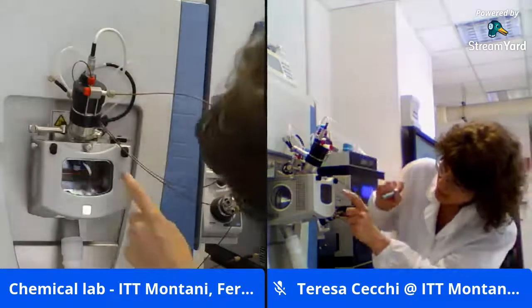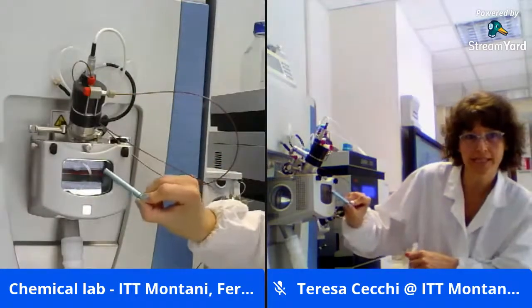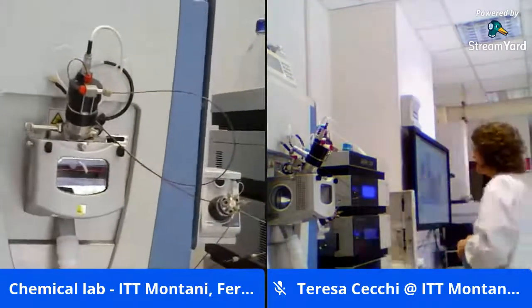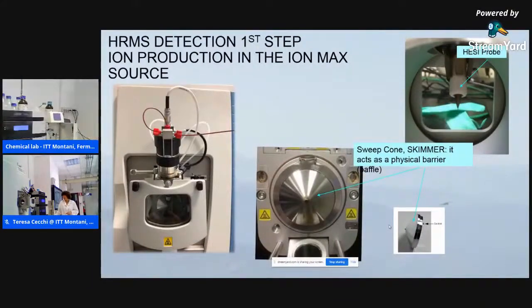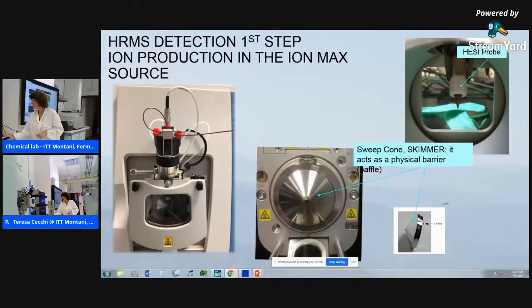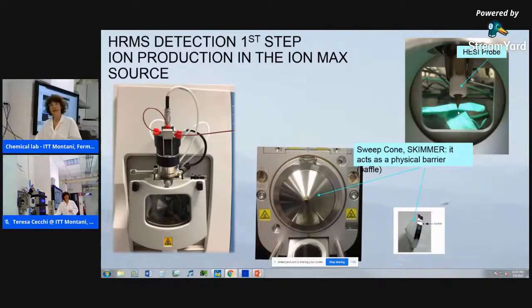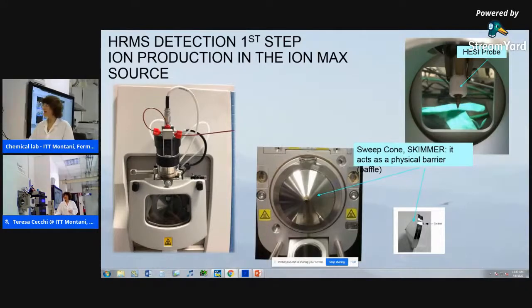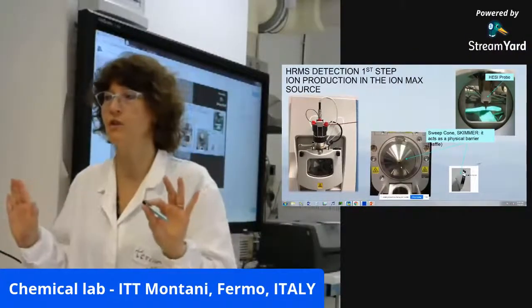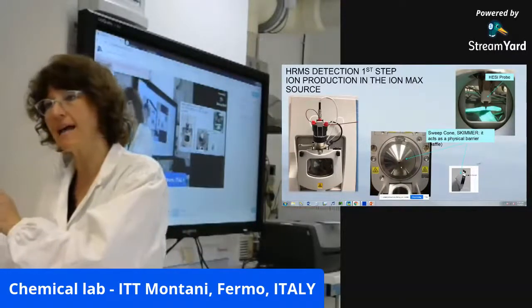In both cases, the probe ends with a nozzle, and now it is not easy to see what is inside, so for the sake of clarity I go back to my slide. You can see the probe nozzle here, where the effluent from the column comes out, and I told you that the voltage is very, very high here. On the other side, I see a sweep cone, which is also a kind of baffle or a skimmer, something that acts as a physical barrier, because we do not want any molecule to get inside the detector. We only want ions to get inside the detector.